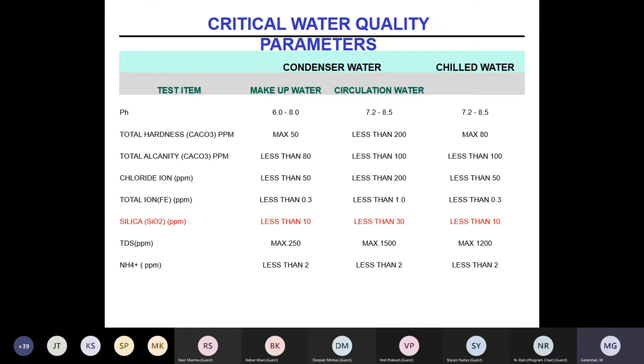Any inefficiency in the cooler and the condenser is going to result in problems for the compressor. So, right from the beginning of commissioning, if you keep this record and track it, we know where we are currently running, and whether descaling is needed after one year or every 3 months. This result will tell you. So please, after commissioning, at the third month, take a water sample, analyse it and keep the record with you. If anything is beyond recommendation, at least bring it to the knowledge of the water treatment people, since every industry maintains water treatment. Then corrective action can be taken before failure, not after. This is the recommended quality, and people were already doing it. Plus or minus, we can do it.